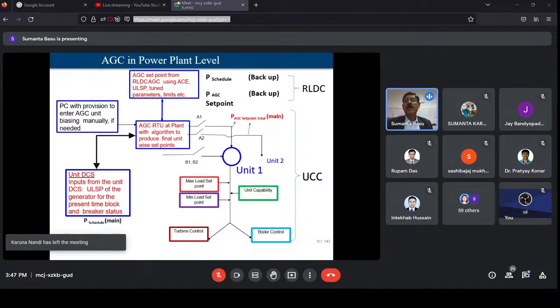So this is how the AGC is implemented at the plant level. This is the AGC unit. This block interacts with your load dispatch center. This is the AGC RTU unit at the plant level, with a particle swarm algorithm being used for prediction. It takes input from the plant control and takes the set points from RLDC, and compares the scheduled generation and the AGC generation. Based on that, the unit maximum load generation set point and minimum load generation set point are set automatically under unit capability, and accordingly it controls the turbine and the boiler. So this is the complete stabilization technique, and it is a proven technique.